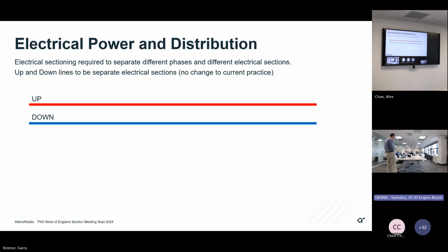So let's look at what's needed for the electrical function. And I laughed when I saw this slide, Paul, because it's almost too simple. But one of the key requirements is that every track has its own electrical circuit. We generally don't common up tracks, because if you get a fault on the up, you lose the down as well. So we're not sitting here saying we should common the whole lot up to save money. We keep that separate electrical section clearly. It's also a requirement for the protection system, which is quite an important influence on what you do with sectioning. For the protection system to work correctly, you need the two lines to be separated.